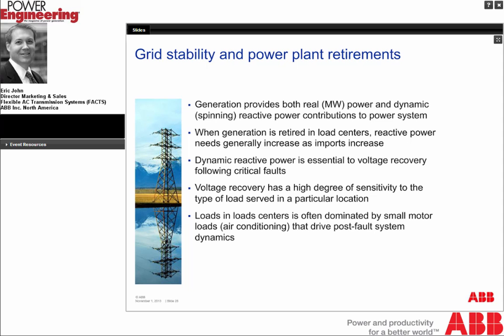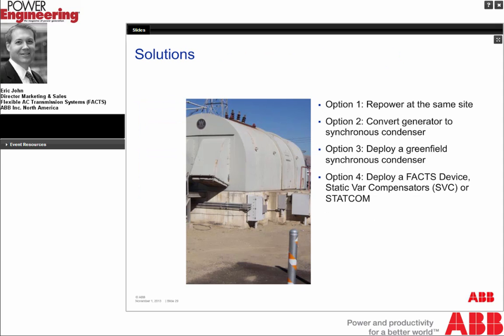Another point is that dynamic reactive power is essential to voltage recovery following critical faults. And that voltage recovery has a high degree of sensitivity to the type of load served in a particular location. Loads in load centers, like a city center, are often dominated by small motor loads such as air conditioning. And those small motor loads drive the post-fault system dynamics. So summarizing these points, we can jump in and talk about the solutions.